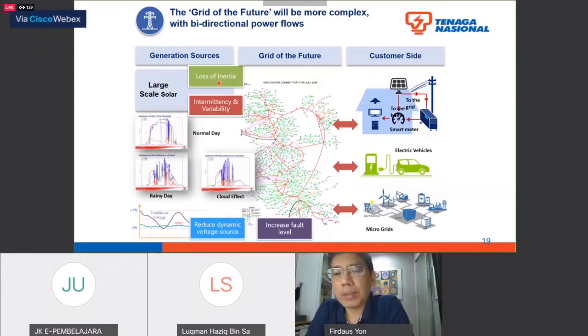In the UK there was a blackout in London because of this. There was a fault, the system did not have enough inertia, and it cascaded into a blackout for the London region. Interestingly, the National Grid at the time was actually piloting measurement of system inertia, so you might want to look into that as well. It's quite interesting how we measure inertia, because if we know the inertia of a system, we know what to do to mitigate certain contingencies. Not knowing the capability of the system to withstand a fault makes us blind in terms of operations - we cannot prepare for it.